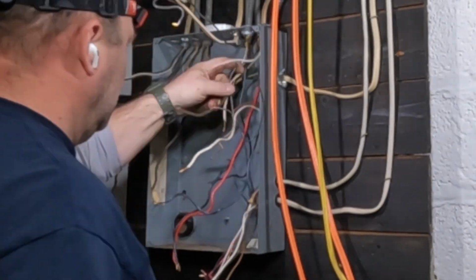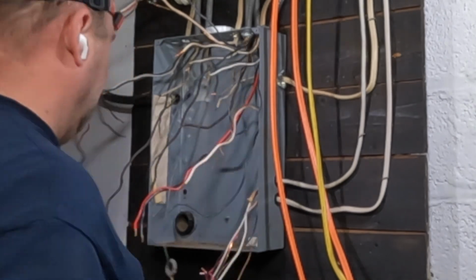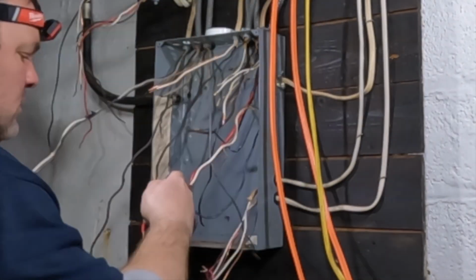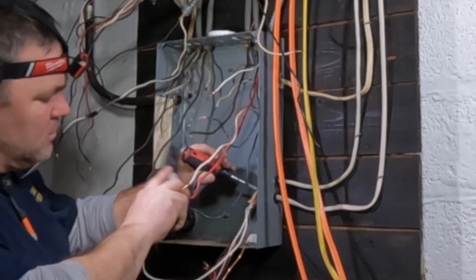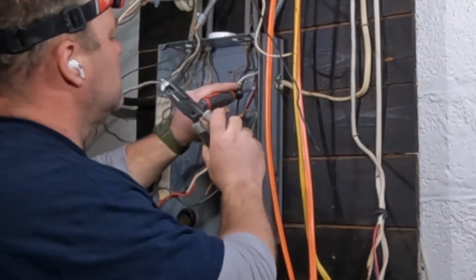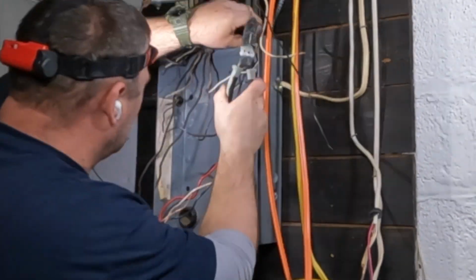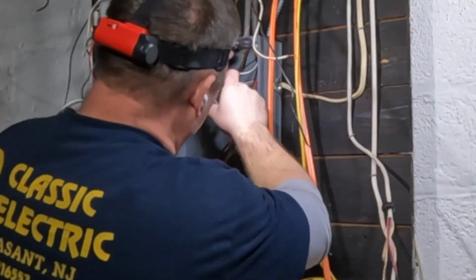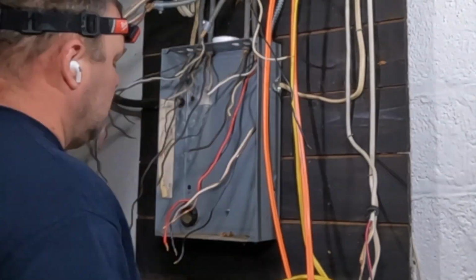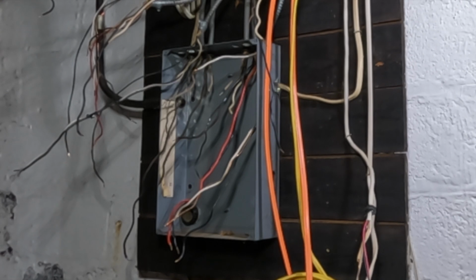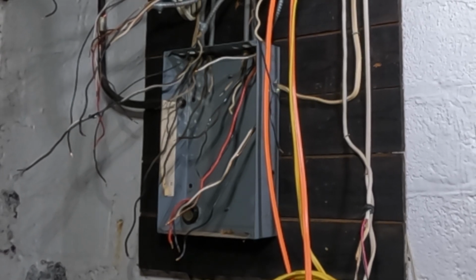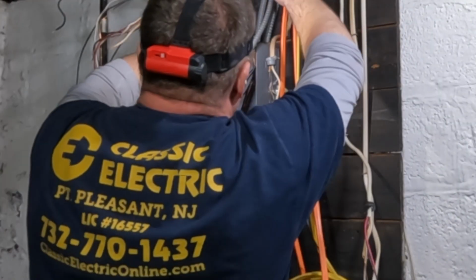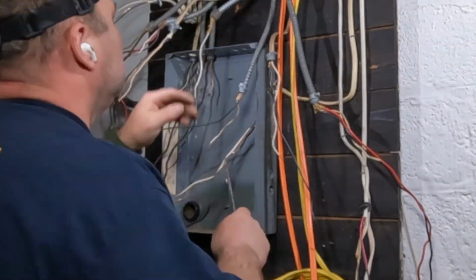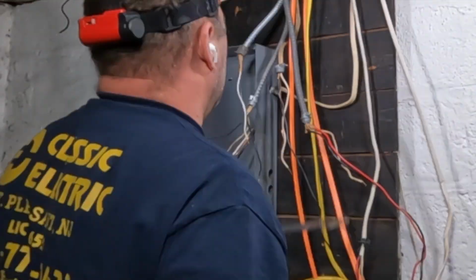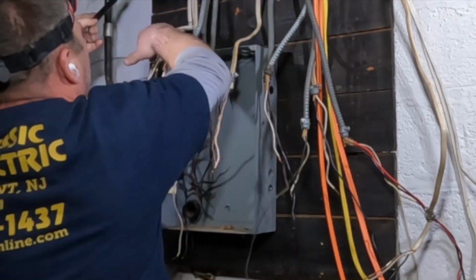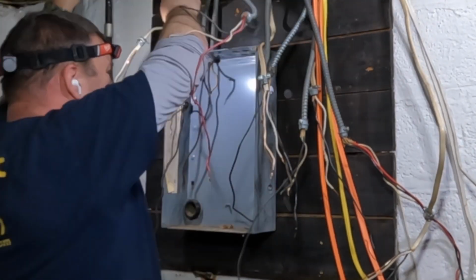So delicately I remove all of the grounds, all of the hot conductors. Then of course we want to make sure that we label all of our double pole circuit breakers somehow, so that when we put the cables back into the new panel, we know that they're connected to a 240 volt double pole circuit breaker. So that's also important. I like to use vinyl tape to wrap both the conductors that go to the breaker, so I know which ones get attached to the double pole circuit breakers. So we got a combination here of non-metallic sheathed cable, the Romex that you see, and of course at the top all the original armored BX cable.